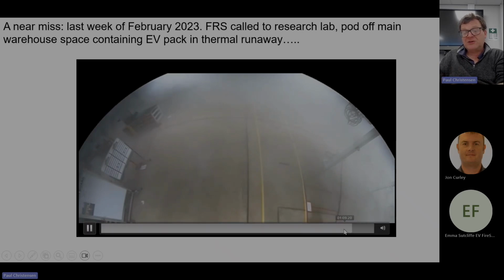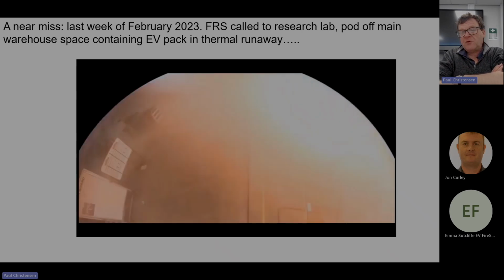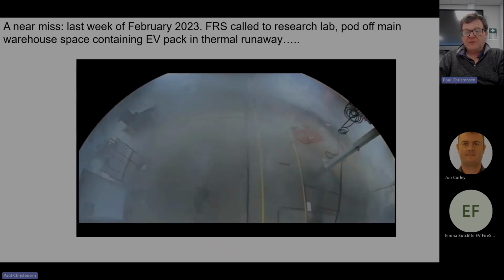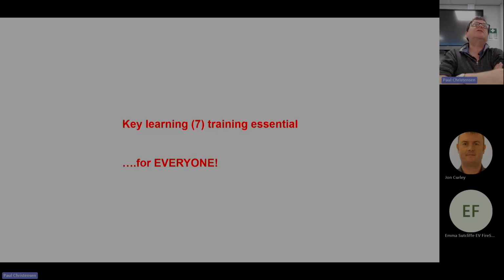It used, by the way, CO2 suppression, 4 times before that happened. Now, the owners of the facility should have known better than to use CO2 suppression. If you kill the fire, but you do not stop thermal propagation, you switch the hazard from fire to explosion.